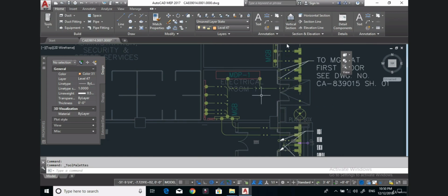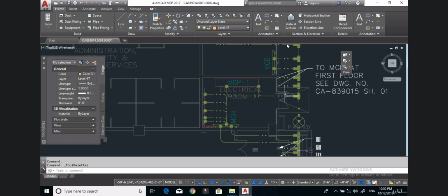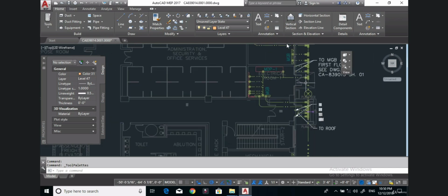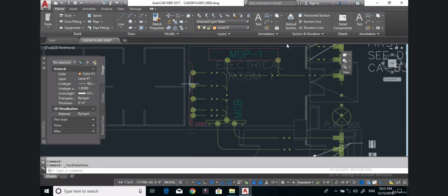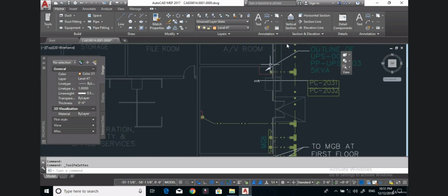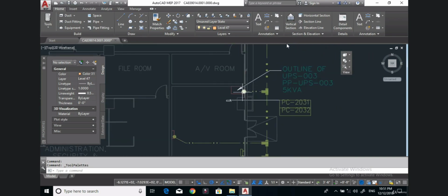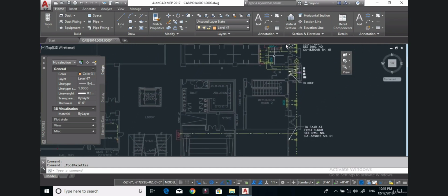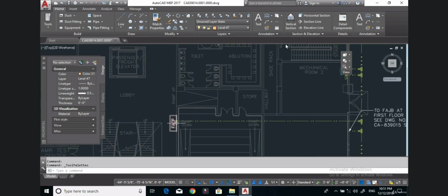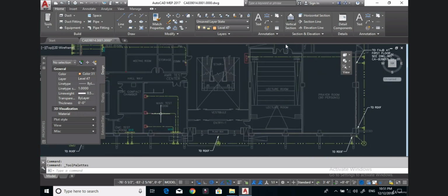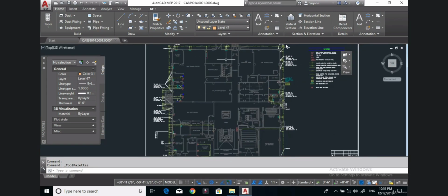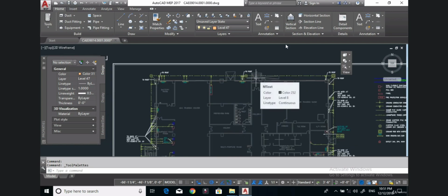And if we move here to the electrical room, also I have many cables coming from the loop cable. This is 35 mm cable, and I take it directly to the final distribution panel here. And also I have two cables for the FDB. See here also I have a UPS unit. I take a conductor also from the loop. And here for the fire alarm control panel also I take a 35 mm conductor from the loop to the FACP panel and so on. As I'm saying, you can use this drawing as a guideline for your next grounding and earthing design.